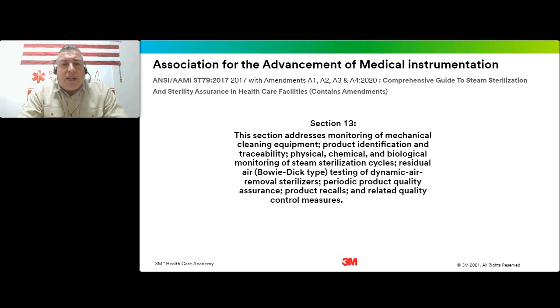In section 13 of the AAMI document, ST-79, you'll see that this addresses the monitoring and mechanical cleaning of all the equipment, product ID, those are our load labels, traceability, physical, chemical, biological monitoring, residual air removal or Bowie-Dick test as a lot of us refer to it, testing of the dynamic air removal sterilizers, and then periodic product quality assurance, product recalls, related quality control measures. So that's where this is all derived from.